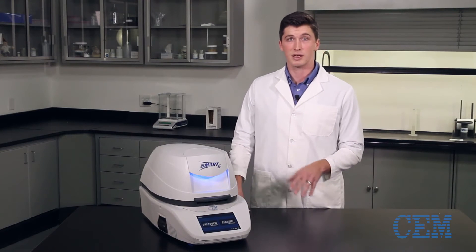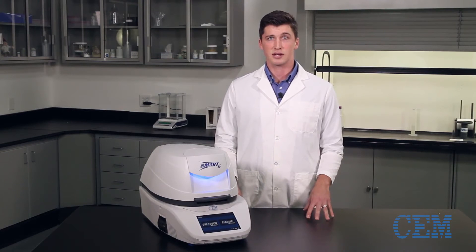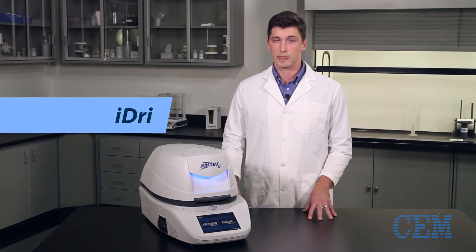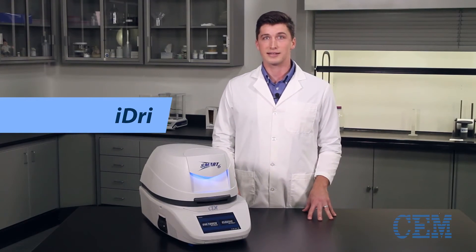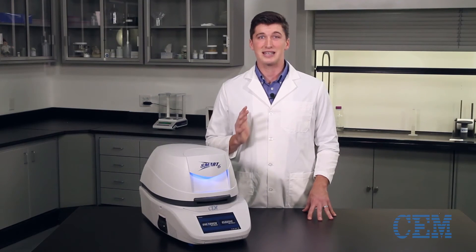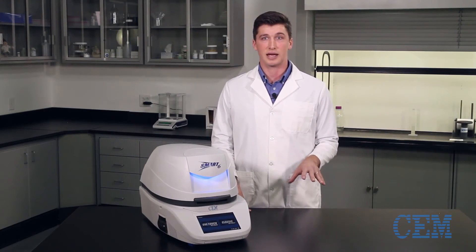One-touch technology takes things a step further, by offering a library of optimized CEM methods for little or no method development, along with the breakthrough new iDri. iDri is an advanced analysis that can further reduce test times, with results in only 60 to 90 seconds for any sample — less than half of the previously possible test times using other direct analysis technologies.